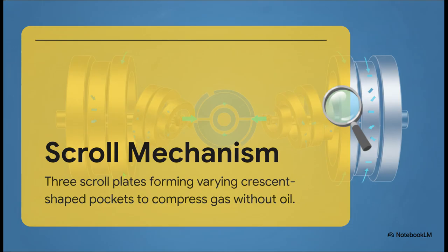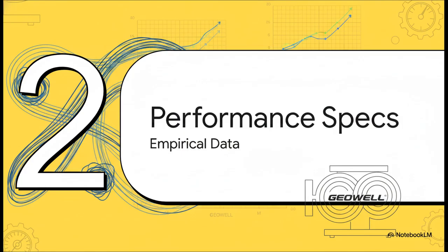Well, the secret sauce is a highly precise 3-scroll plate design inside the pump head. You've got one central orbiting plate moving between two fixed scroll plates, offset by exactly 180 degrees. As it orbits, it creates these crescent-shaped compression pockets that progressively change size. Gas gets pulled into the outer pockets, compressed right toward the center, and then smoothly discharged. It's just pure, brilliant mechanical geometry doing all the heavy lifting. No friction fluids required. Moving right along to Section 2, Performance Specifications.